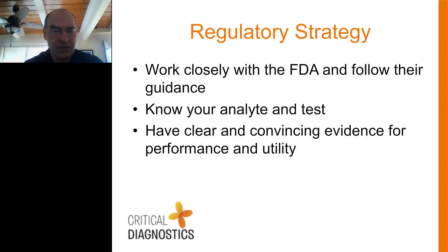Okay, because the FDA is focused on 2 things, primarily on safety. Is this test going to, if a decision is made on the test, is there a risk to the patient? So you have to be able to answer that question. You have to show that the risk is understood if there is risk and what the consequences will be. And then is it clinically useful? That's less of a question for the FDA. That's more of a question for CMS. But it's an important question for you as a developer of a product to show that not only do you get safety and effectiveness, but there's utility.